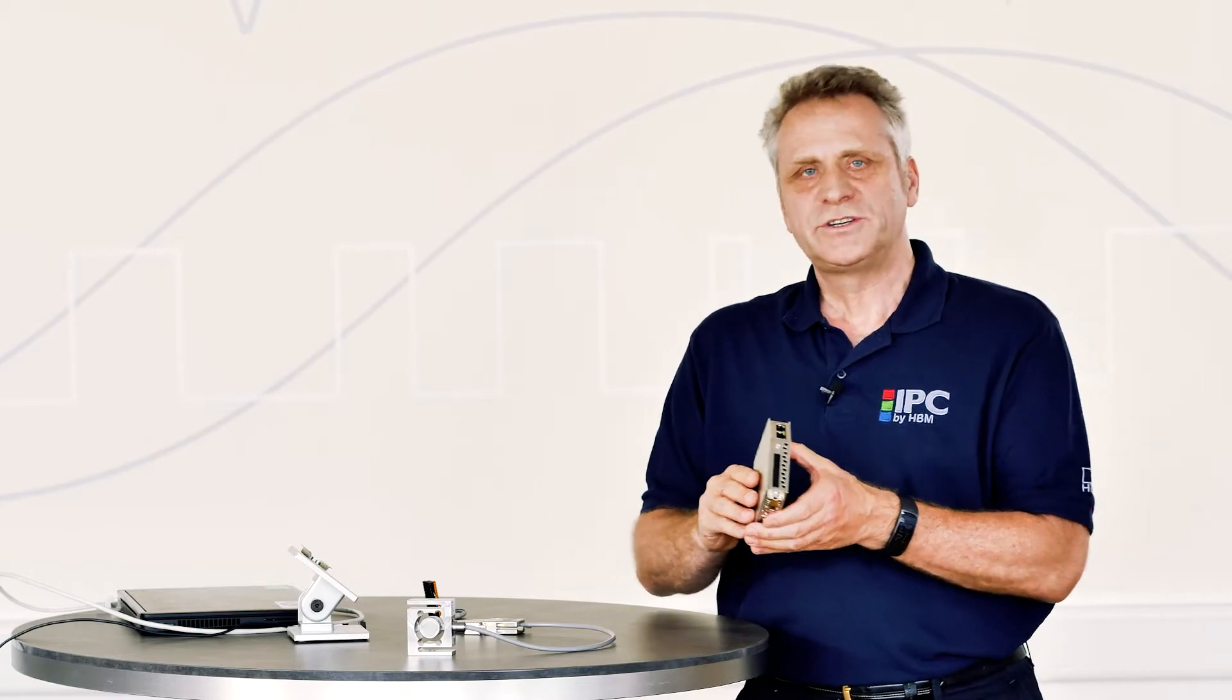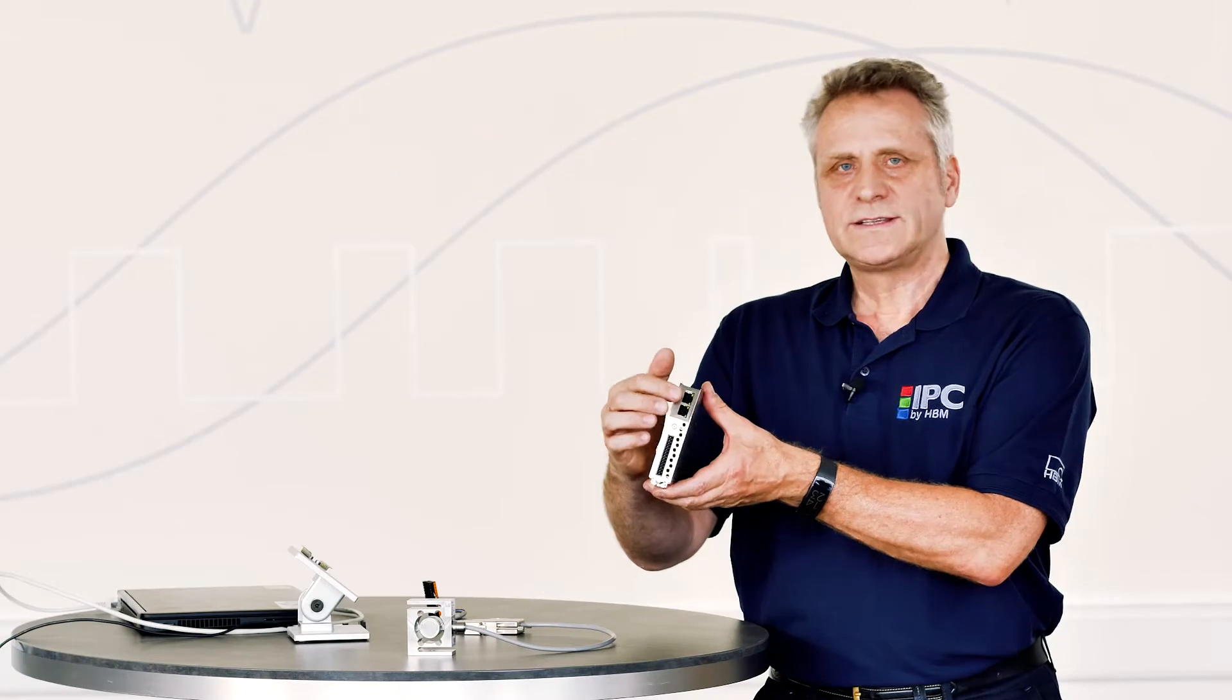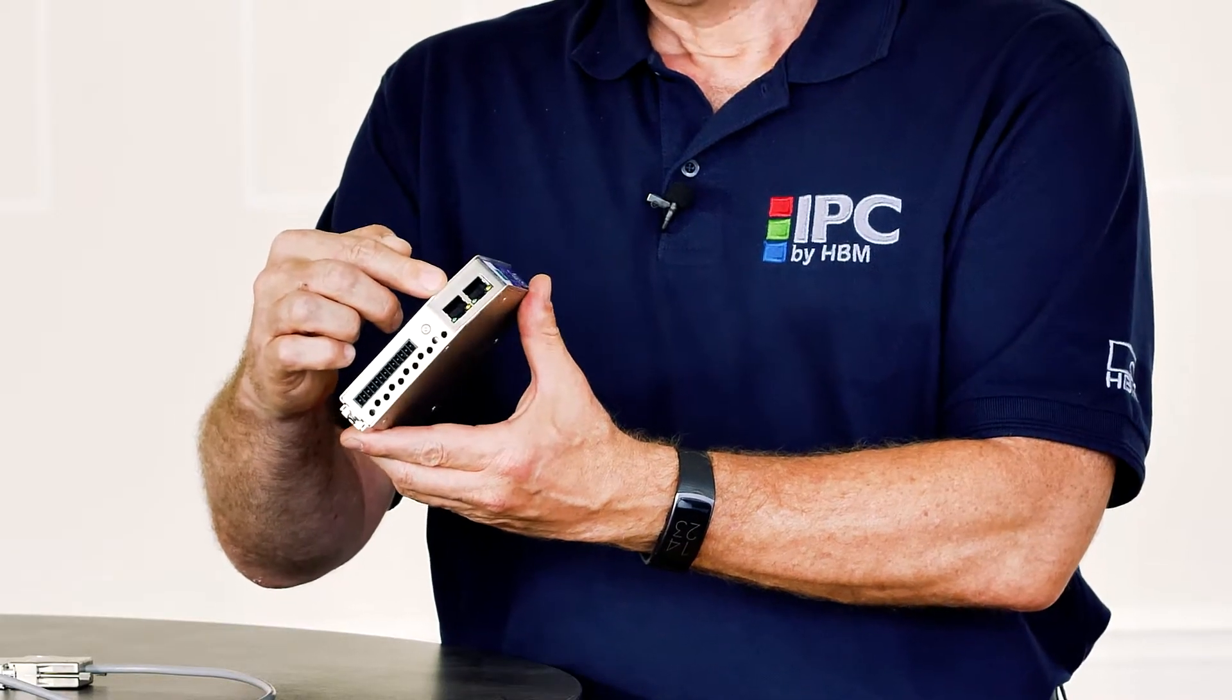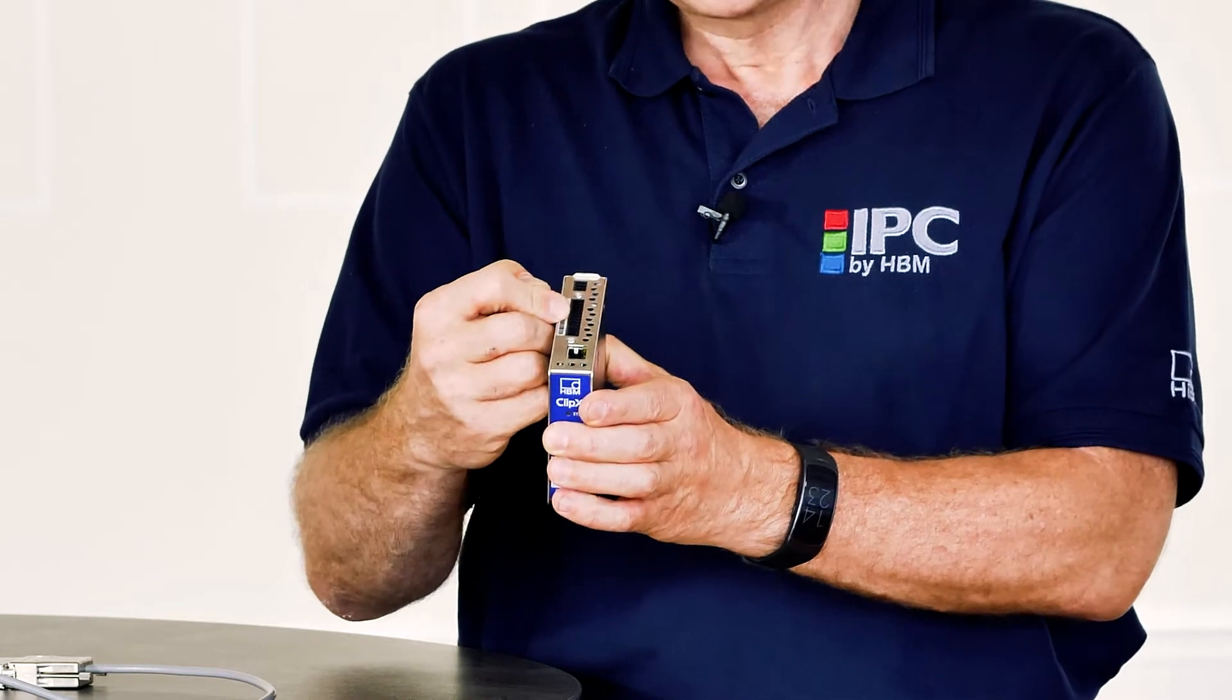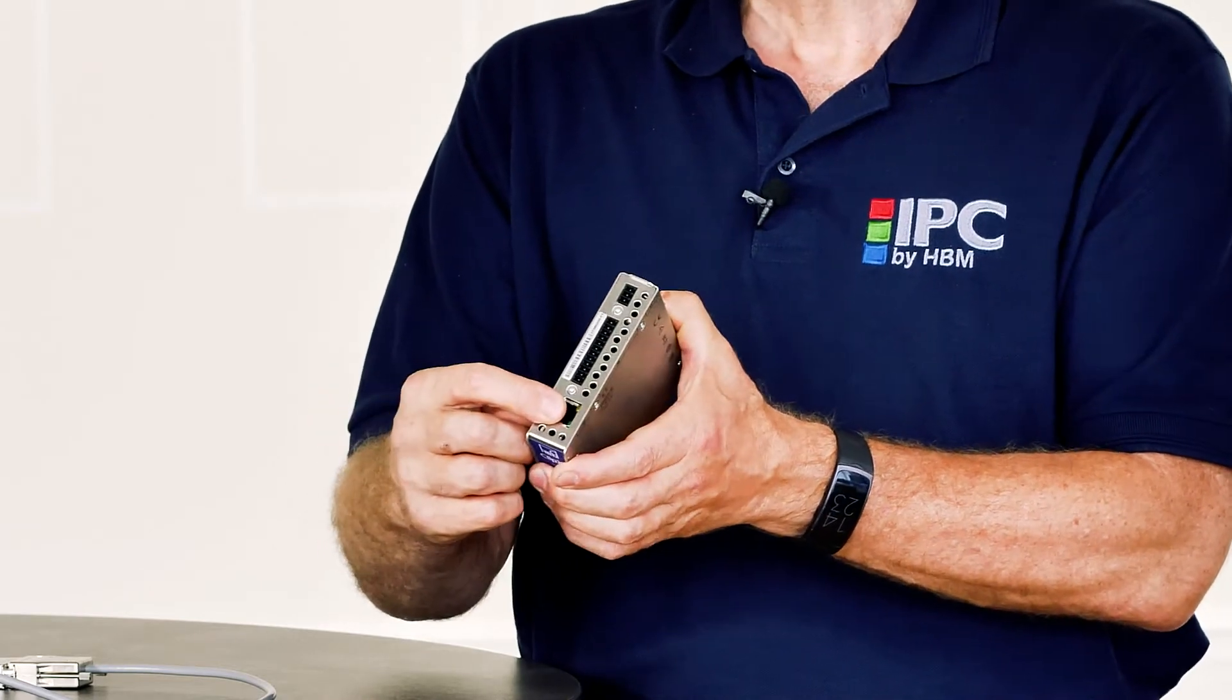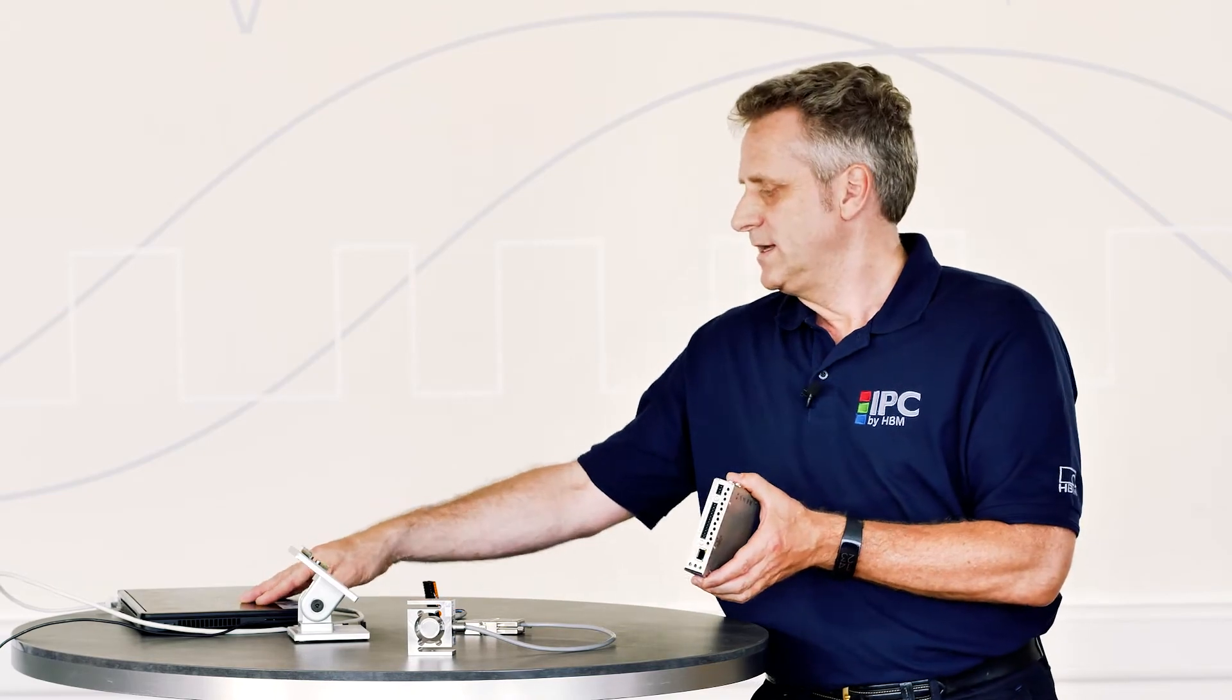ClipX has seven different sensor inputs. The first sensor input is located at the bottom of the device. In addition, ClipX has field buses, meaning that PLC controls can be integrated here. On the top, there are connections to the power supply as well as to the digital inputs and outputs and the analog output. Our parameterization interface is a standard Ethernet interface that can be accessed via any browser-based device, such as a PC, laptop or a mobile phone.